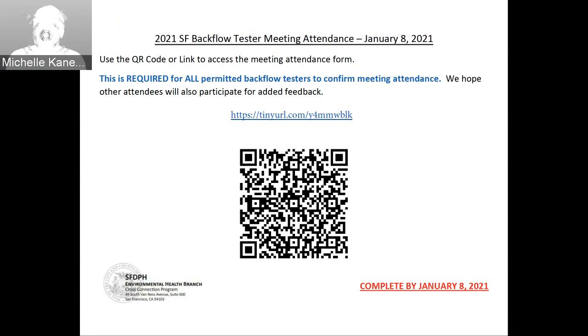I think people were using it as a way of not writing the specific isolation hazard type. We want it in CCAMS to be correctly recorded. So if it's a boiler assembly, even if it's on the standard service, we want to make sure that it is showing as a boiler and not just as standard. It gets very complicated, especially when we're trying to deactivate or remove an assembly and it just says standard and we don't know what it was tied to. So that's why we want to make sure that the more specific hazard type is listed, and that people are selecting boiler or some other type that is the actual hazard. And then, as Montian stated, if it is actually due to the height of the building, there is still that option.